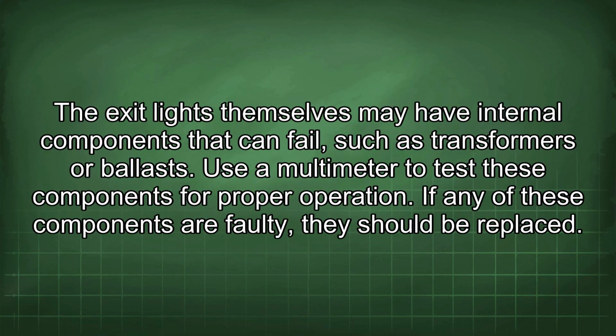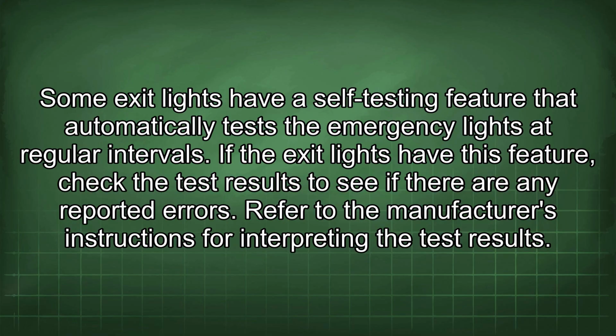The exit lights themselves may have internal components that can fail, such as transformers or ballasts. Use a multimeter to test these components for proper operation. If any of these components are faulty, they should be replaced. Some exit lights have a self-testing feature that automatically tests the emergency lights at regular intervals. If the exit lights have this feature, check the test results to see if there are any reported errors. Refer to the manufacturer's instructions for interpreting the test results.